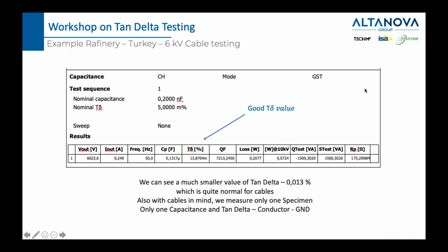I don't know if you remember the studies of electronics, you have electrons and you have the holes. And when you have an electrical field between them, then even though you might have a semiconductor or an insulator, there are some free electrons inside, and as they move, they do conduct a little bit. So at 12 kilovolts, this all stops, and you shouldn't have any additional conductivity, or your tan delta should be the same.